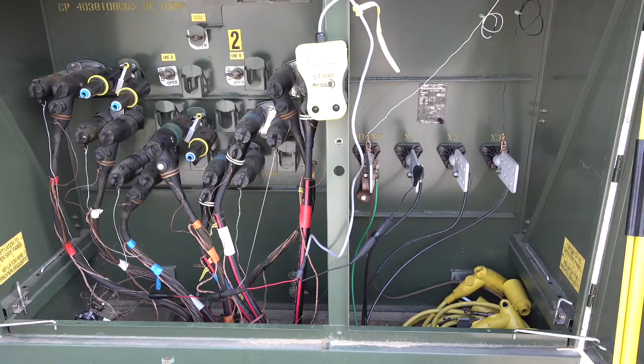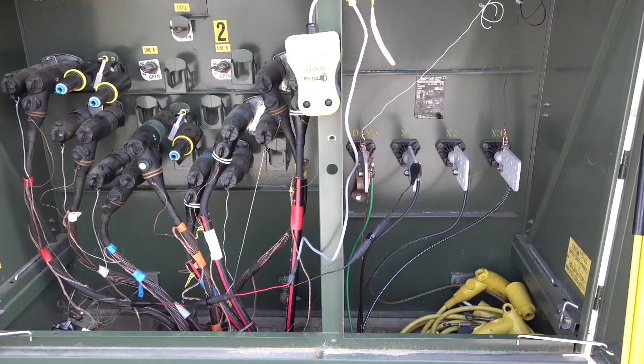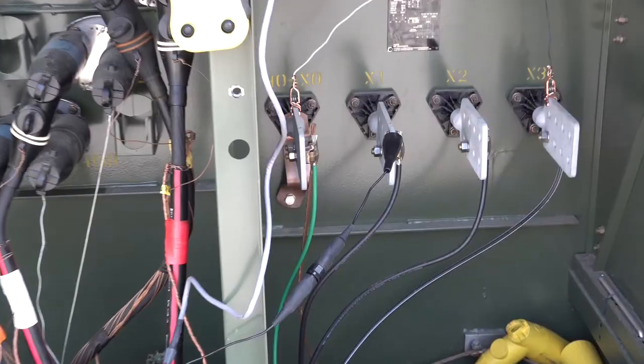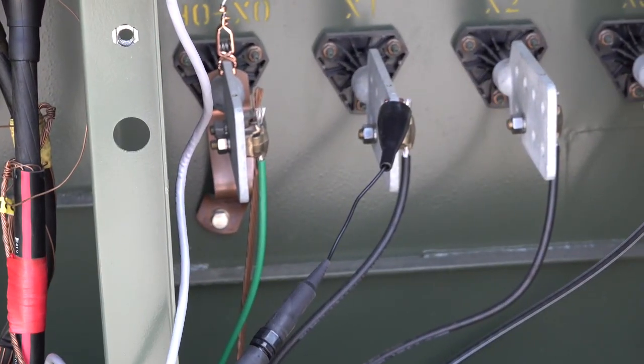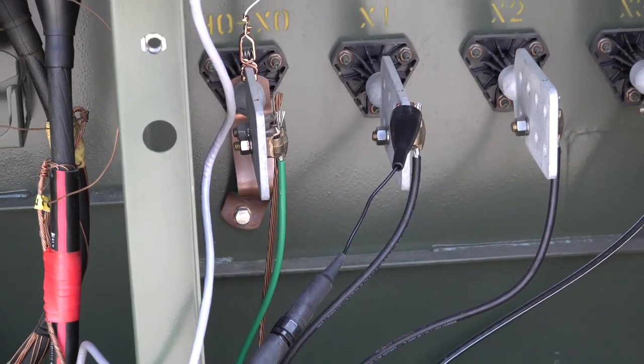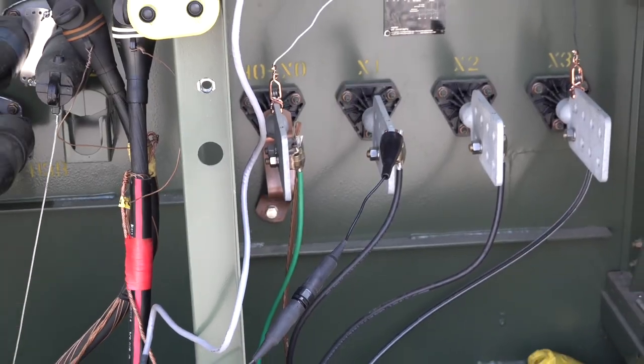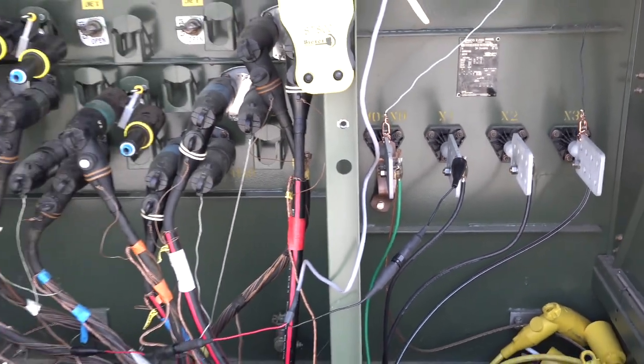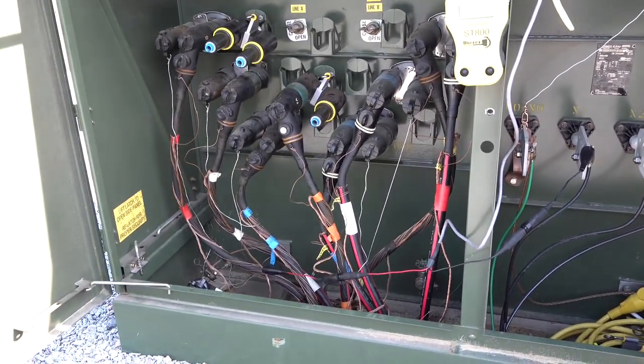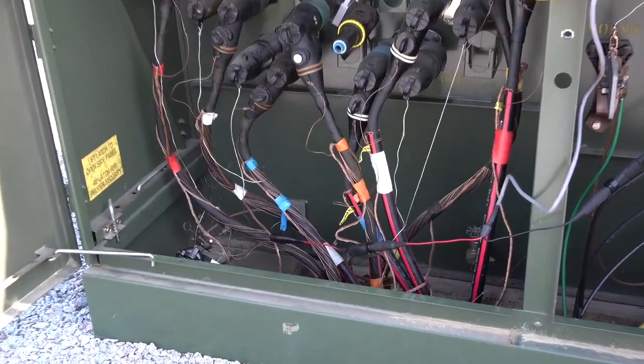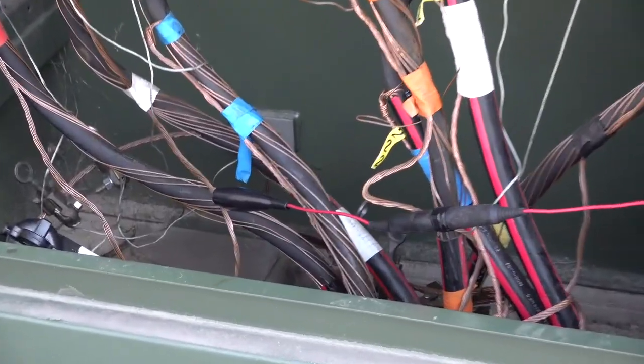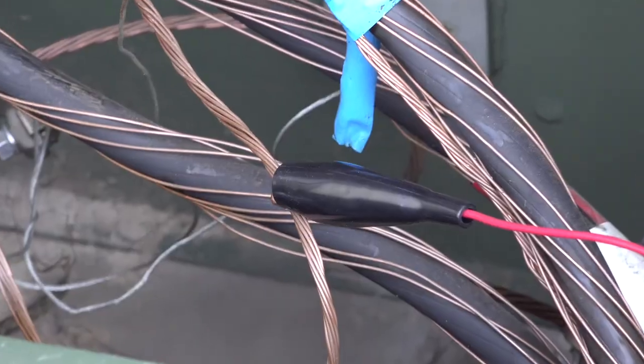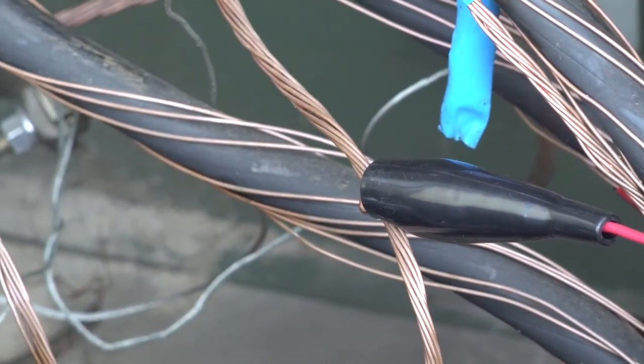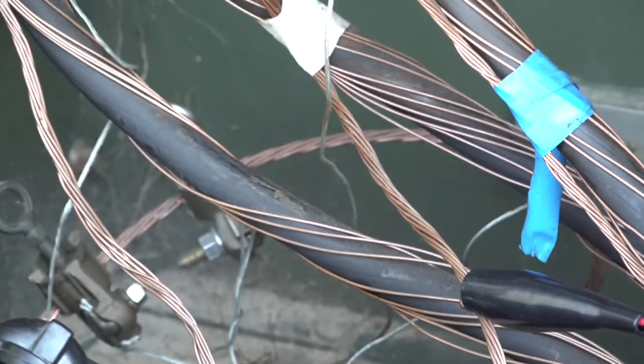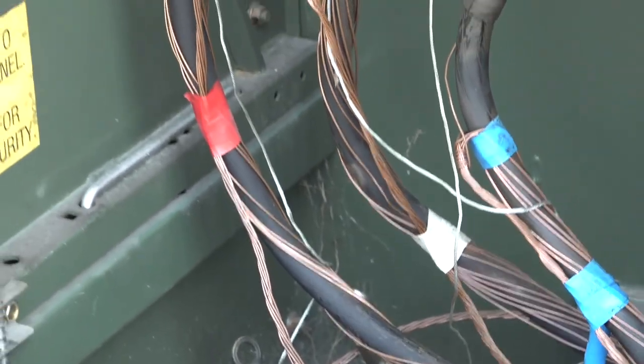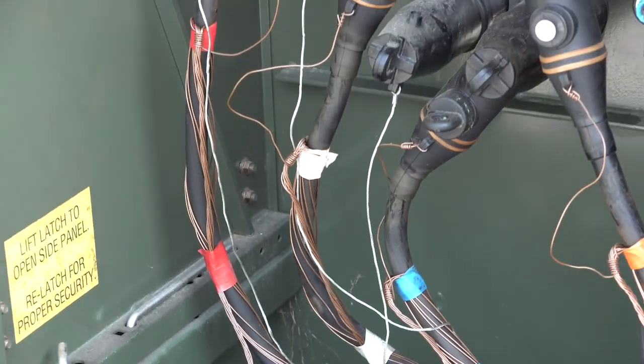Our next demonstration is to identify energized primary cable. Notice our connections are the same as when we identified de-energized primary cable, with the black lead connected to the secondary power and our red lead connected to the concentric of the energized primary cable we want to identify in a manhole or a ditch. Notice this cable is not de-energized and is in fact energized to 13,800 volts.